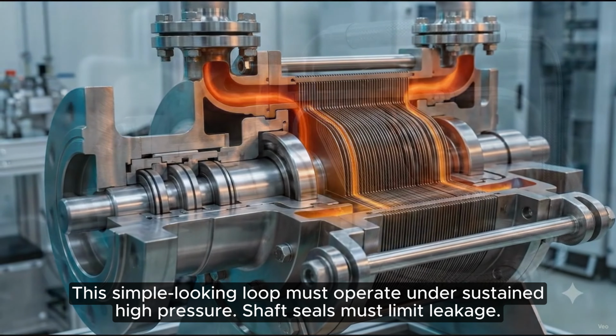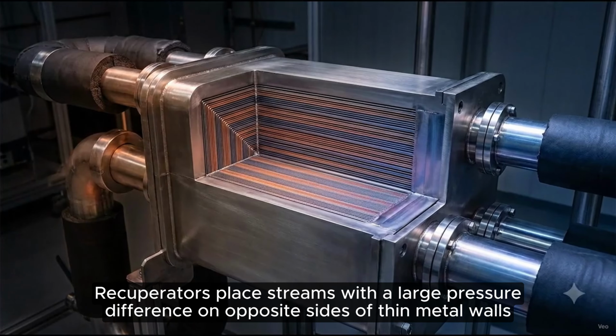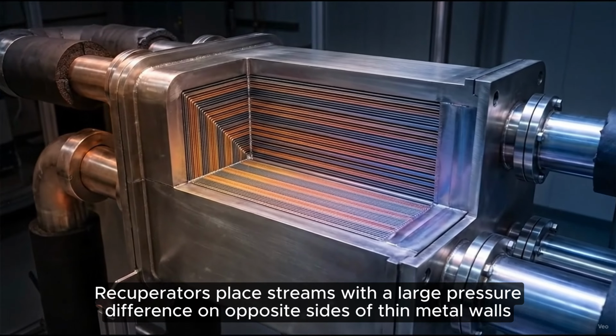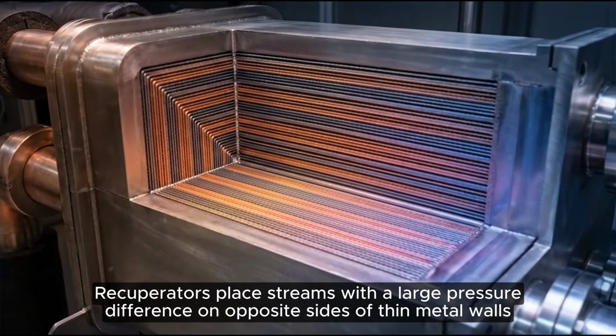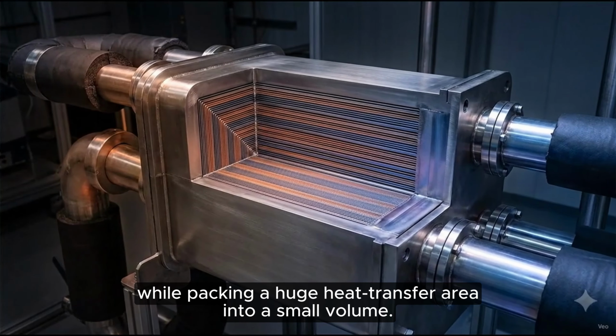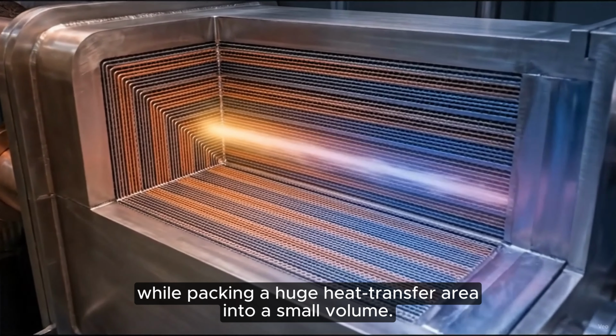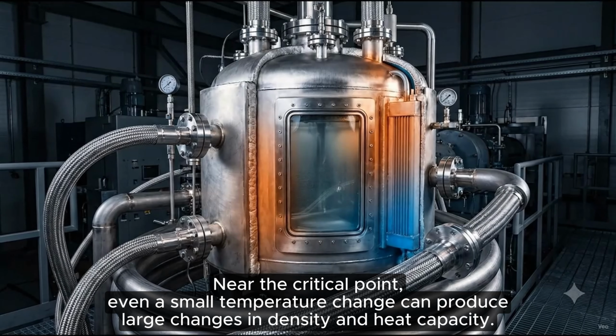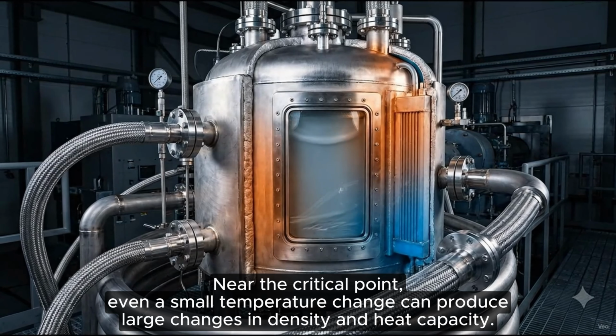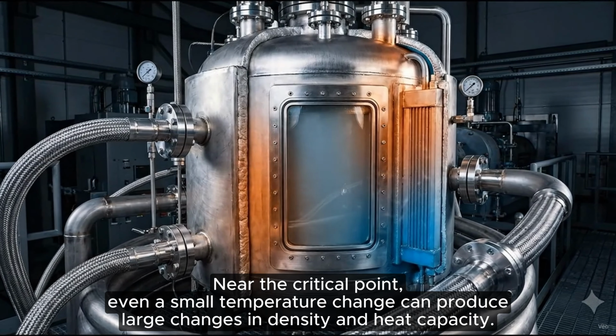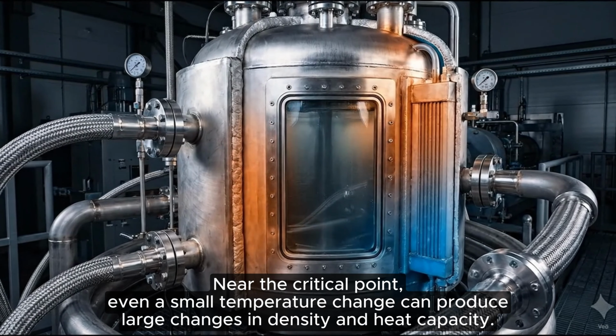Shaft seals must limit leakage. Recuperators place streams with a large pressure difference on opposite sides of thin metal walls, while packing a huge heat transfer area into a small volume. Near the critical point, even a small temperature change can produce large changes in density and heat capacity.